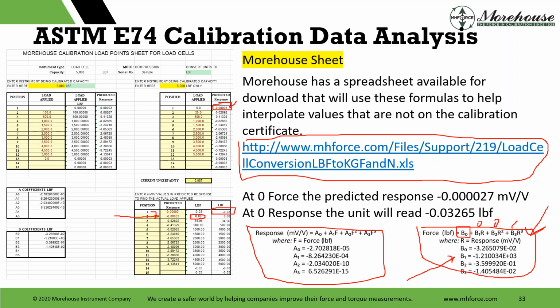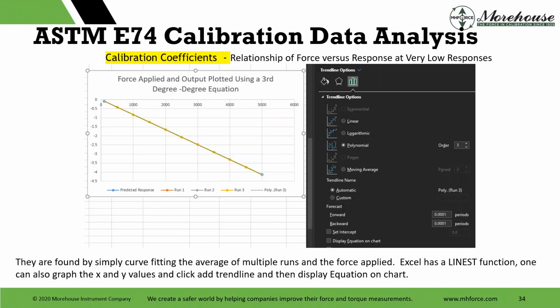So that this number becomes 0 at 0. This number becomes 0 at 0. This number becomes 0 at 0. But the B0 isn't multiplied by any response. So therefore, when that indicator is zeroed out, whatever the B0 value is what the indicator will read when using that equation. So this relationship of force versus response at very low responses, here we go. They are found by simply curve fitting the average of multiple runs and the force applied. If you want to do this in Excel, it has a LINEST function. One can also graph the X and Y values and click add a trend line and then display the equation on the chart. That's essentially what we're doing here.